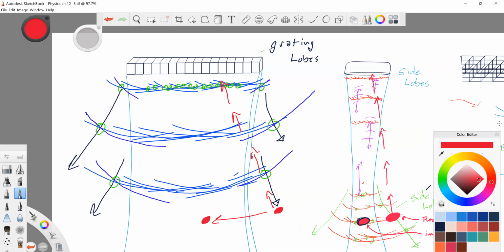Of course, this is an exceedingly wide beam and an exceedingly small object, but you get the idea. This is, so it thinks, dotted line, that's what it thinks happened, because we violate an assumption. The assumption is that all sound comes from the beam, or all echoes come from exactly where the beam is. And unfortunately, that's not the way it is all the time.